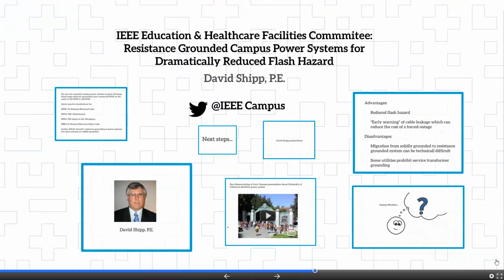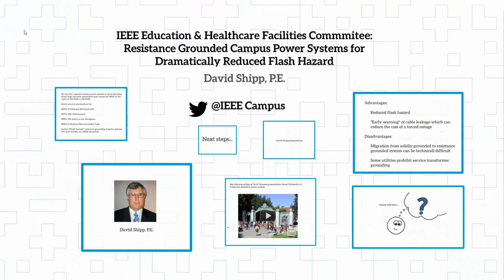Now, having said that, it's super easy to retrofit a solidly grounded system to make it high resistance as long as you meet the code requirements. I just have to make sure I get rid of all my 277 volt lighting loads or so, because I can't run line to neutral loads if I'm other than solidly grounded. Yeah, so there are some issues and things to do on that, but it's not super expensive. When you start from scratch with a new hospital, we can do that.